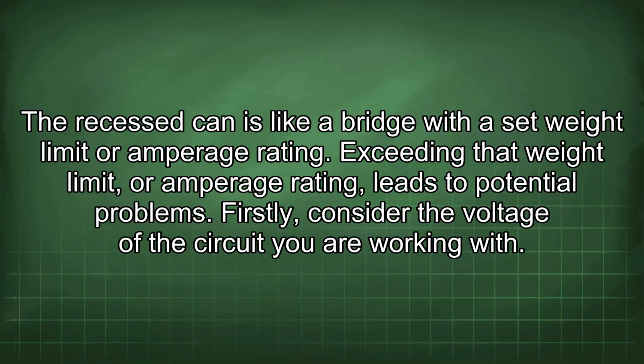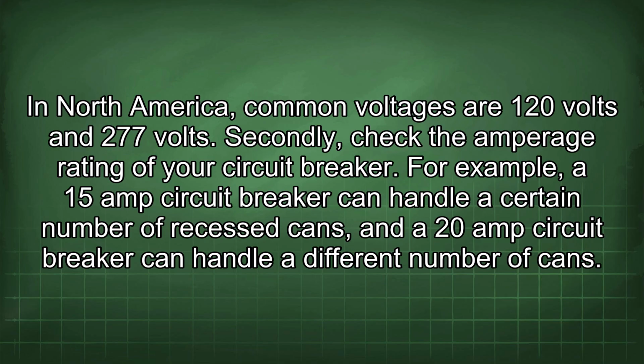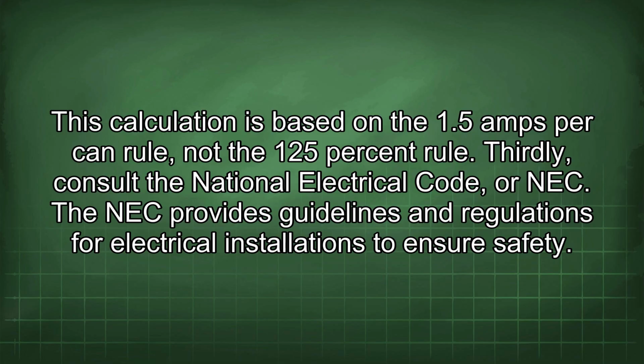Firstly, consider the voltage of the circuit you are working with. In North America, common voltages are 120 volts and 277 volts. Secondly, check the amperage rating of your circuit breaker. For example, a 15 amp circuit breaker can handle a certain number of recessed cans, and a 20 amp circuit breaker can handle a different number of cans. This calculation is based on the 1.5 amps per can rule, not the 125% rule.